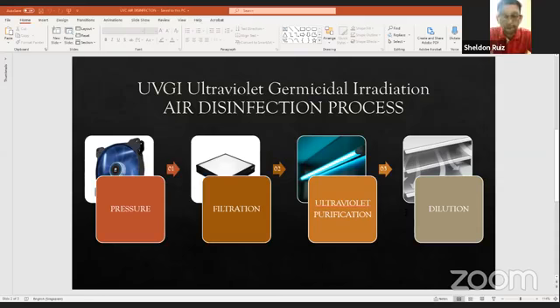And so you need to have, and this product is calculated based on building codes. I mean, all these building codes on air change, and also by area, how much CFM you require to change the air, and also the applications: what is this room to be used for, and how much CFM of air volume do you need to change and how often. So it's a combination of all, and also looking into the filters, the pressure drop of the filters. You also need to consider this in your design.